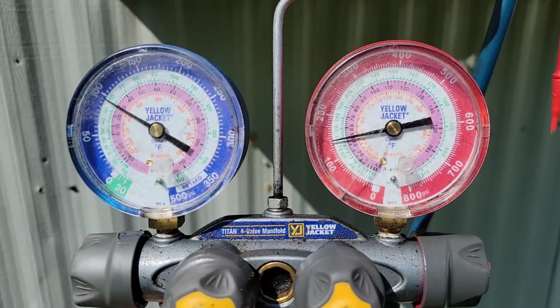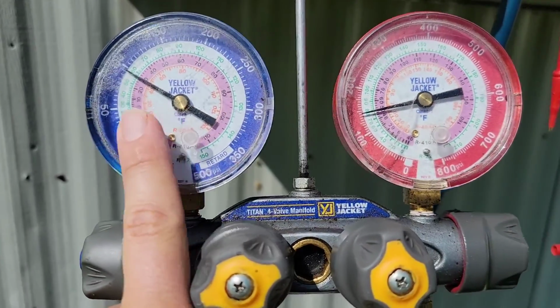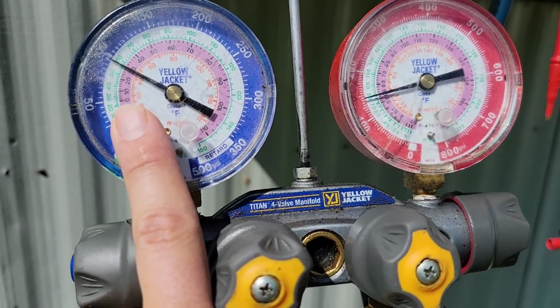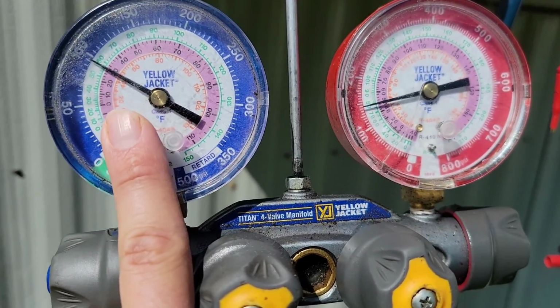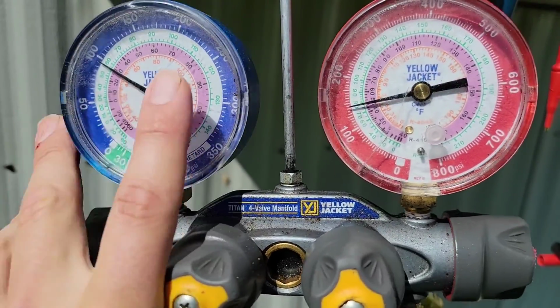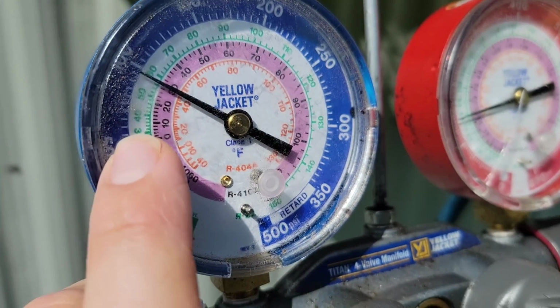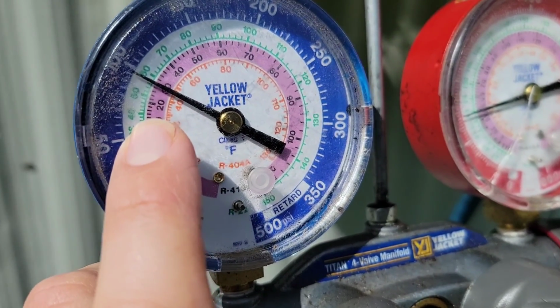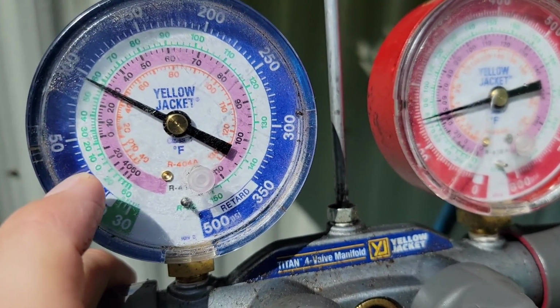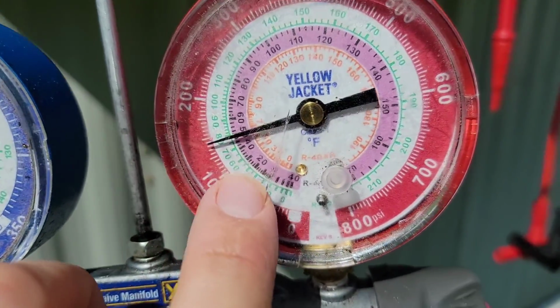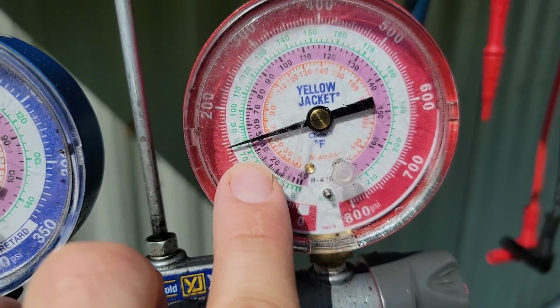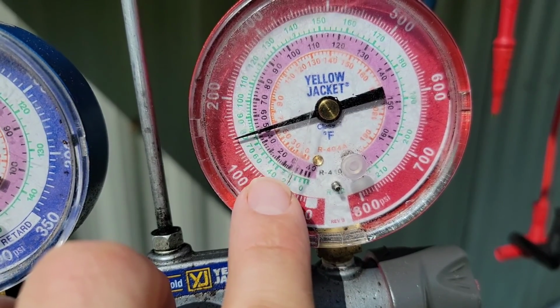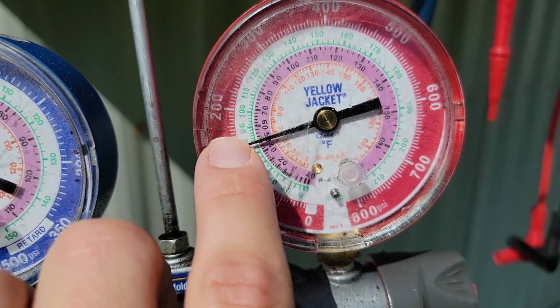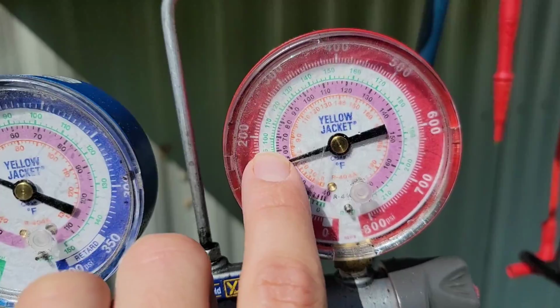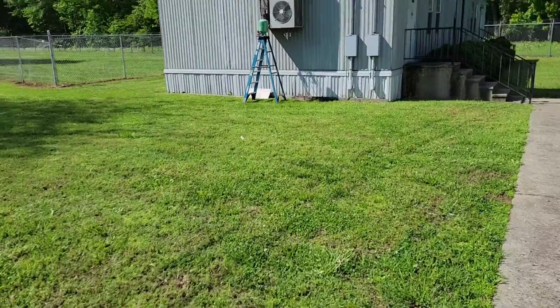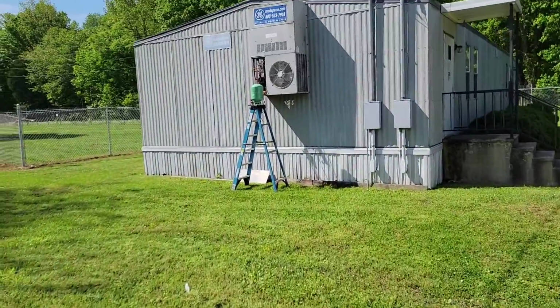So typically the pressures you're going to find in the field for R22 are going to be 70 on the suction. For a perfect 95-degree day, it would be about 70 on the suction right here, which would line up with about 40 on the saturation temperature. And then over here, for R22, it just depends, but I would say around 200 for today. But let's hook it up, let's find out. It's about to come back on. We're going to be able to charge it up.